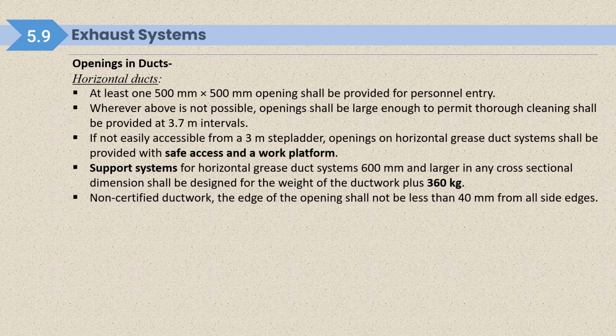If not easily accessible from a 3-meter step ladder, openings on a horizontal grease duct system shall be provided with safe access and a work platform. If the height to reach that opening is more than 3 meters, or it cannot be reached using a 3-meter step ladder, then we need to provide safe access and a work platform. Support systems for horizontal grease duct systems 600 mm and larger in any cross sectional dimension shall be designed for the weight of the ductwork plus 360 kg. So what should be the strength of that support system? That has been mentioned here.